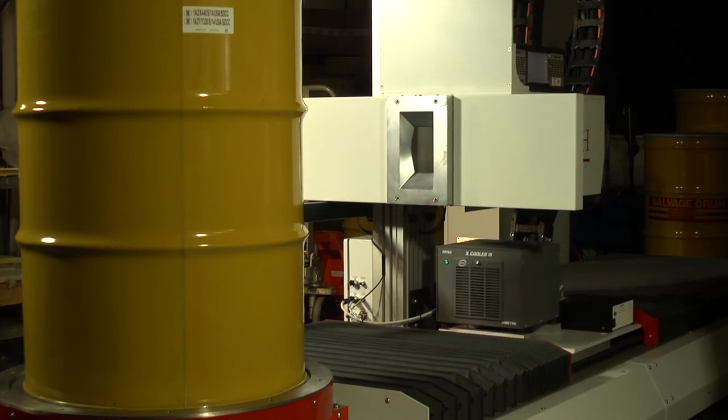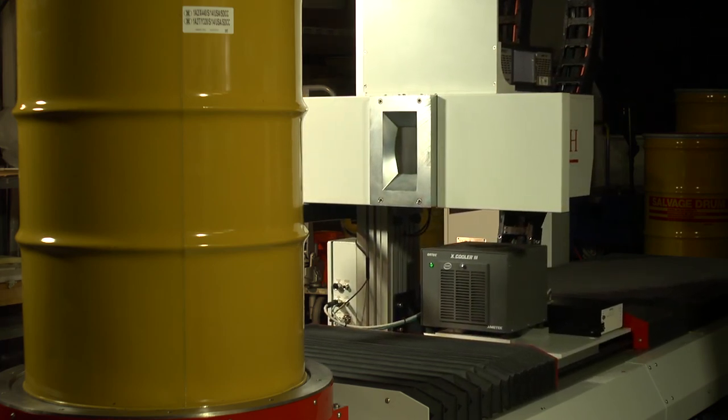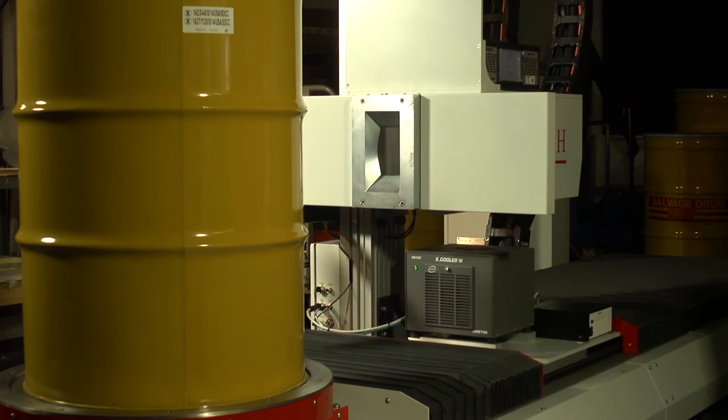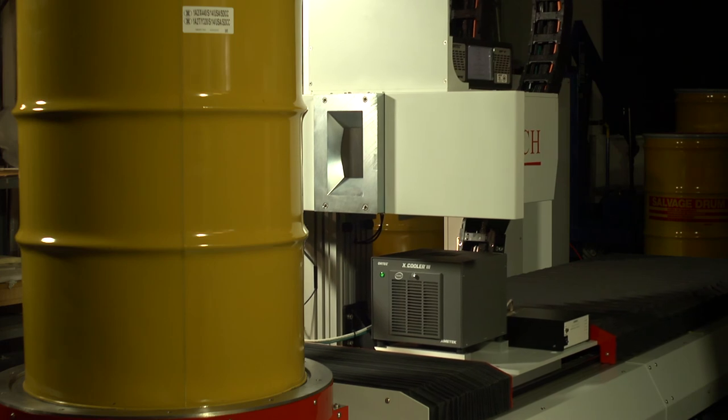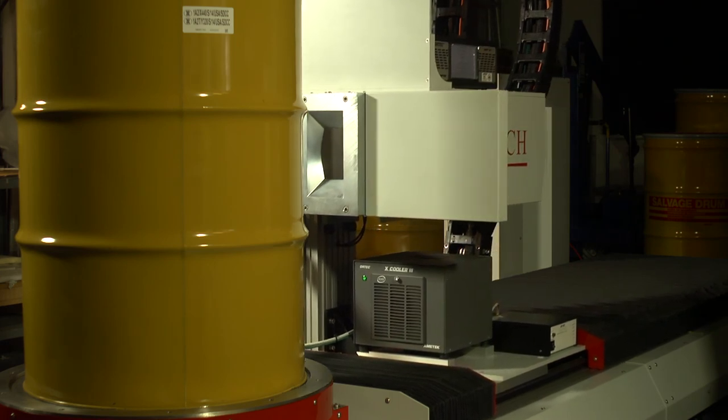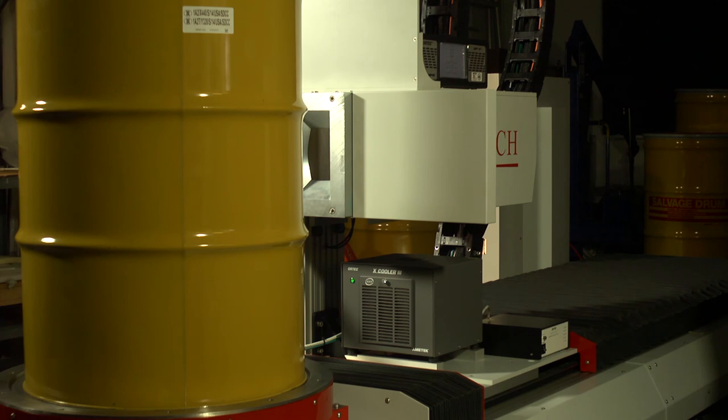The far-field gamma monitor is supplied with a factory calibration which incorporates a benchmarked MCNP Monte Carlo model of the detector response measuring a Europium 152 calibration point source. This source is traceable to international standards.